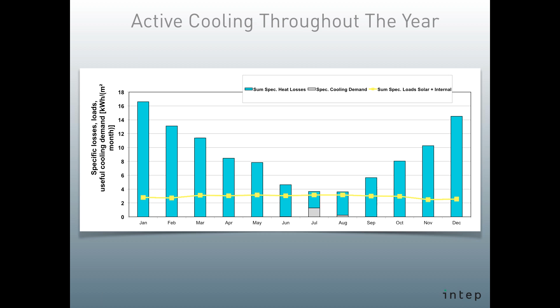And we decided to install a system that can do both. Now, this is something that I think has a lot of potential for the residential scale passive house. The unit in the center at the top there is what's called a slim duct heat pump. So it's essentially an air-to-air heat pump system that can accept a minimal amount of duct work. So that unit gets buried in the ceiling and can receive basically a trunk line and some branch lines to supply the house with heating, and in this case, actually cooling and dehumidification. The unit is wired up and plumbed up to one outdoor unit. We have one of these on the first and second floors, so there's two of them in the house, one exterior unit.